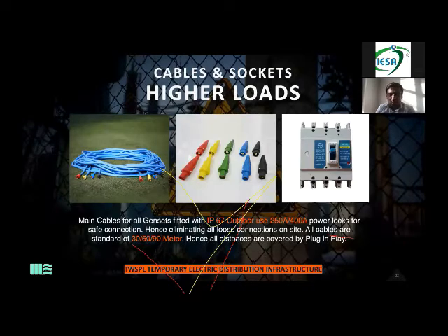So if your load is from 20 kilowatts to 30, 32 kilowatts, you can use a 5-core 10 square mm copper cable. That is recommended for that. If you go to 60 kilowatts, then you can use a 5-core 25 square mm copper cable, and so forth. There is a chart; if you just type on Google, cable rating capacity with amps, you will get that chart. So you can follow that chart every time somebody is asking you for a load, and you can pass it on to your power distribution company that this is the right wire size we want on site.